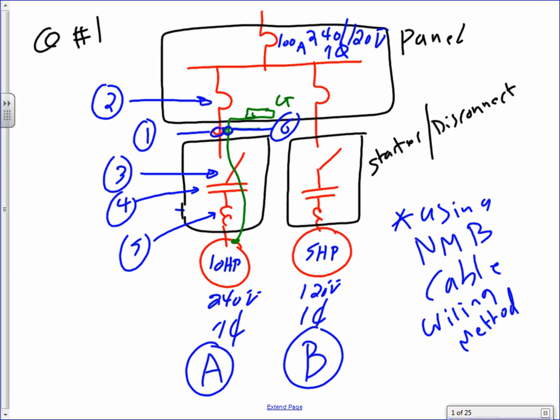A little bit too much for a 10 horsepower 240. And I need to size the branch circuit, the overcurrent device, the disconnect, the controller, the overload, and the equipment grounding conductor for each one of these pumps or fans, anything that has a motor in it. I decided to use a starter/disconnect, guys. There's a combo starter/disconnect that we use, basically a box that has a disconnect on it, and a controller, a magnetic starter, and an overload.